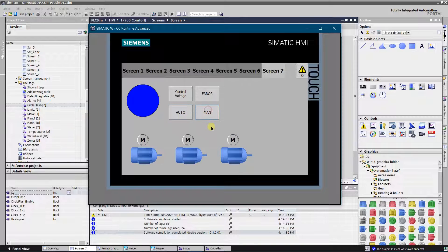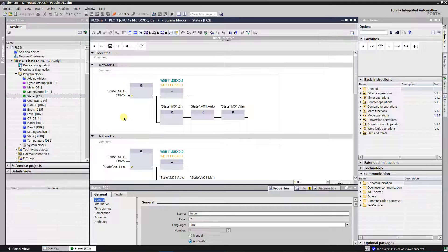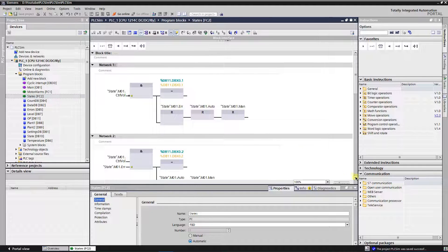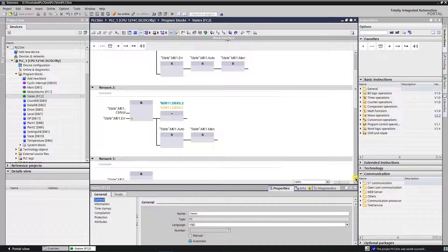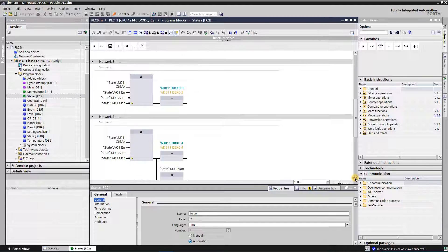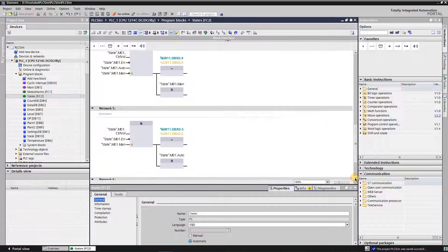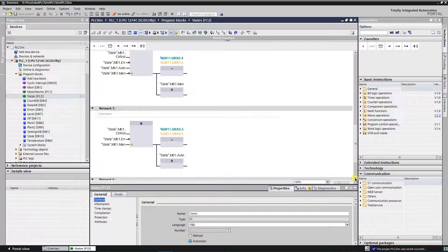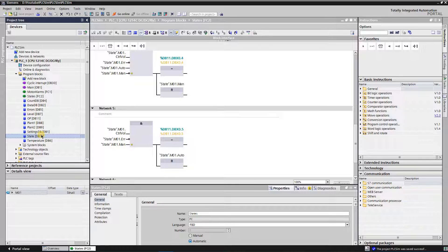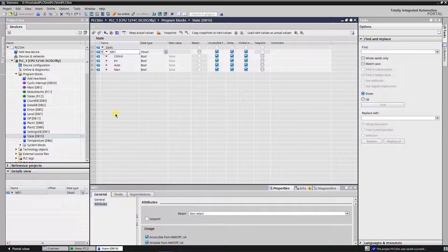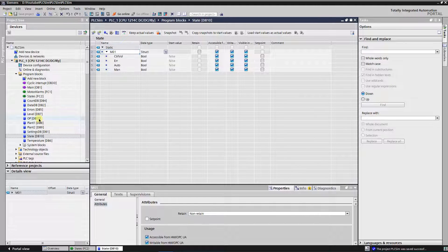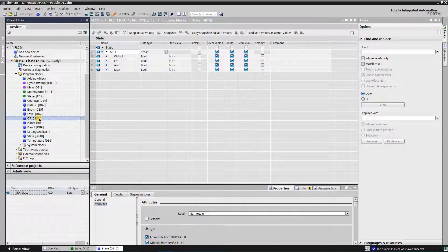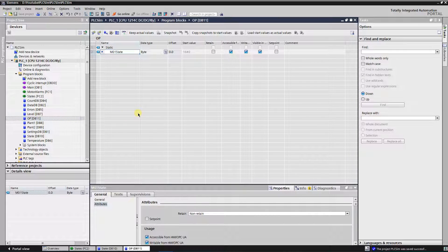At first I will simulate these states in my PLC program. In the first network I do simulate presence of the control voltage. Network number two is used to simulate fault. Network three is used to simulate readiness state. Network four is used to simulate automatic control mode. Network five is used to simulate manual control mode. DB10 contains simulation bits. DB11 contains state of the motor.